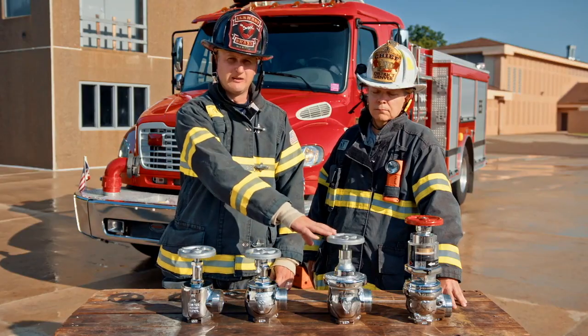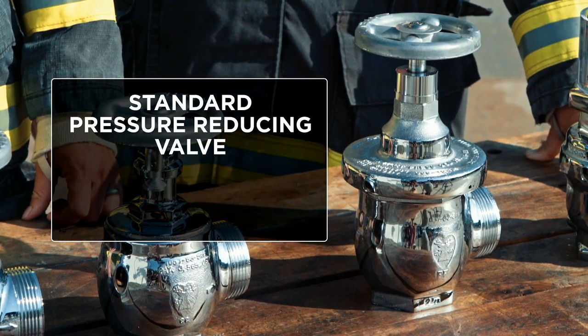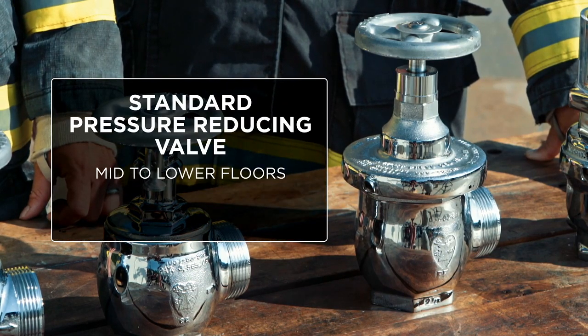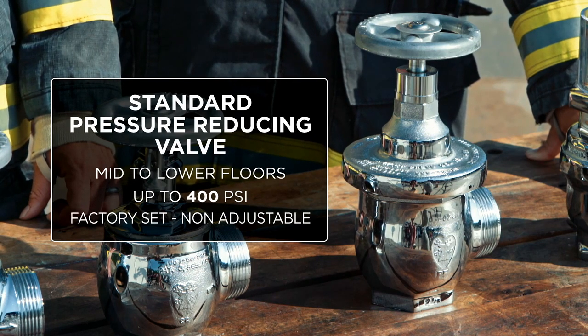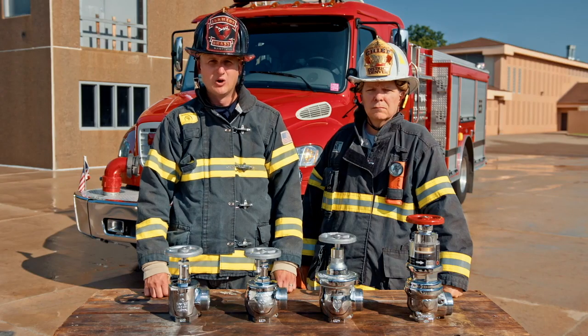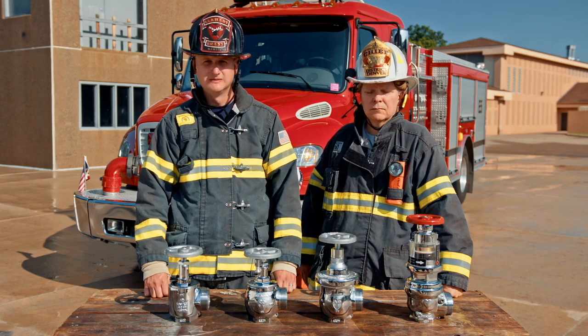The third type of valve is a pressure reducing valve. This is a standard pressure reducing valve that's non-adjustable. You're going to find these in the mid or lower floors, and they're rated for up to 400 PSI. This type of valve is set at the factory, delivered to the construction site, and installed by the installer, hopefully in the right stairwell or floor where this valve has to go.